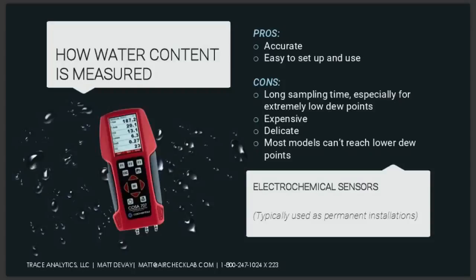The other thing about them, they're kind of expensive and you pay for dew point limits. So if you want to reach, say, a class 2, which would be minus 40 Celsius, you're going to pay a lot more money for an electrochemical dew point sensor that can go that low. They also require calibration. Keep in mind that's a hidden cost that you're going to have to deal with, and something that's going to essentially shut you down on that particular point of use until you can get it calibrated. One more thing to have in line for an audit.